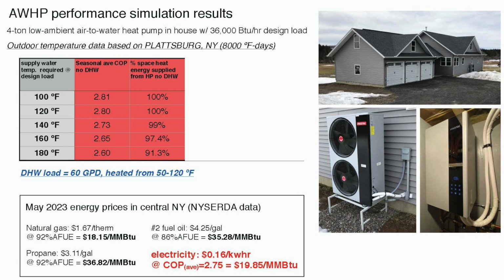Okay, and I just want to show you, these are our costs in upstate New York now. At 16 cents a kilowatt hour and an average COP of 2.75, we're at just under $20 per million BTUs delivered. And that's competitive with where gas is right now. Gas prices are fluctuating wildly. Propane is way up there. Last winter in upstate New York, propane was $5 US per gallon. And fuel oil got as high as, it went over $5 a gallon. It fluctuates. But I want to show you that energy supplied from an air-to-water heat pump in a cold climate is competitive against other fuel options.